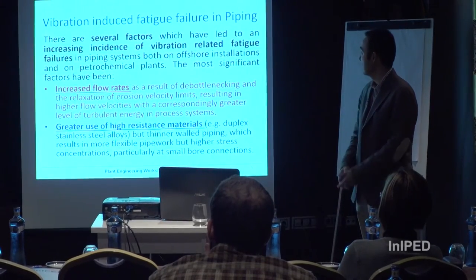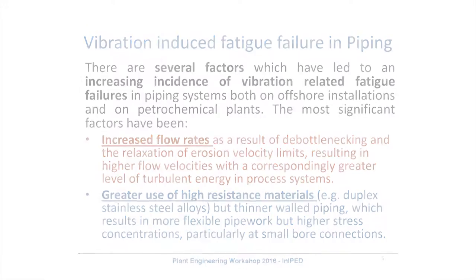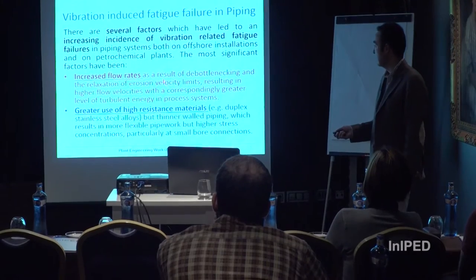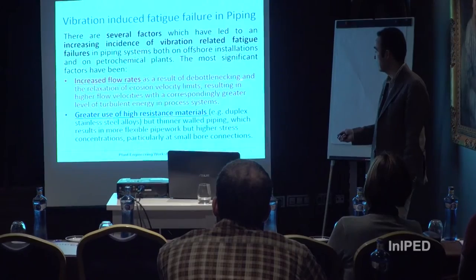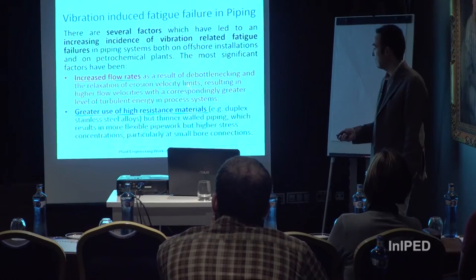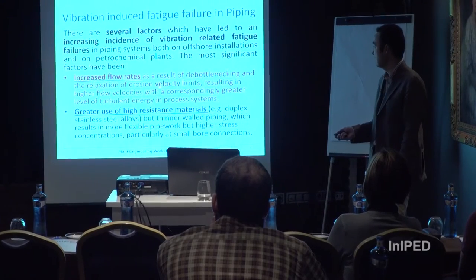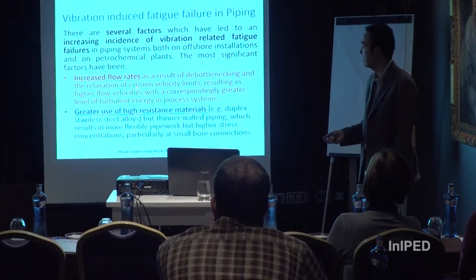There are several factors that have increased the incidence of vibration-induced fatigue failures. The most significant is increased flow rates — we try to improve and get more production from the same plants, maybe running at higher rates than originally designed, as a result of bottleneck studies to improve production of existing plants. This involves relaxation of erosion velocity limits established by good engineering practice, resulting in higher flows, higher turbulence, and more energy in the process lines.